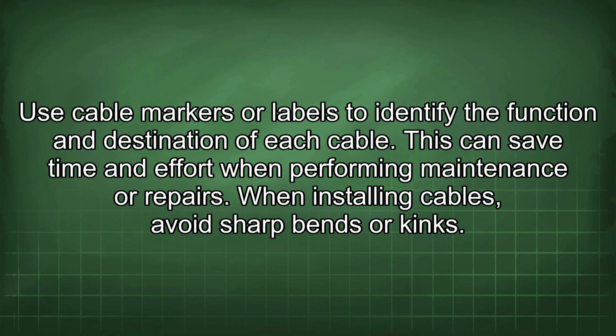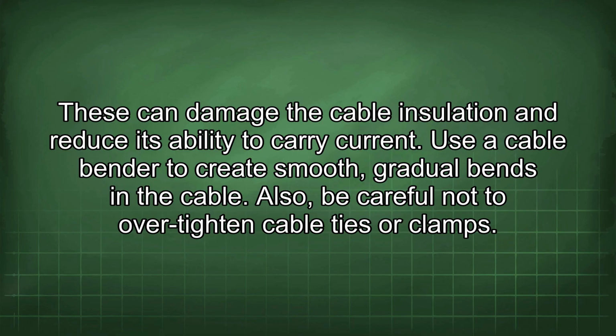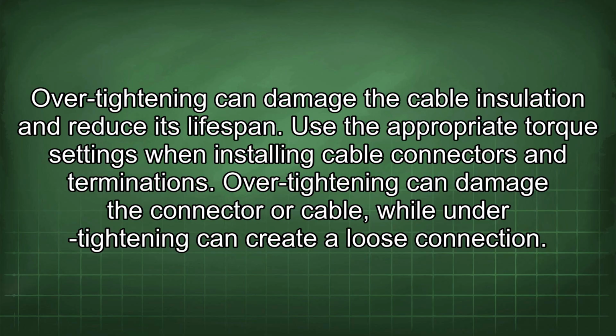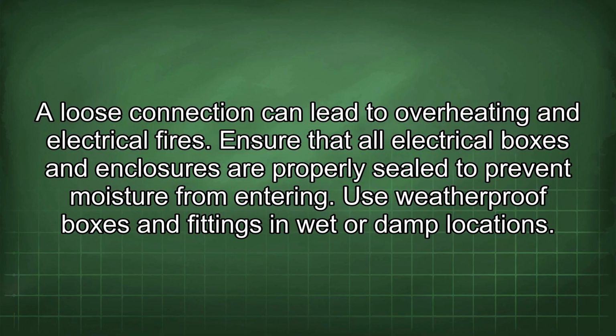When installing cables, avoid sharp bends or kinks. These can damage the cable insulation and reduce its ability to carry current. Use a cable bender to create smooth, gradual bends in the cable. Also, be careful not to over-tighten cable ties or clamps. Over-tightening can damage the cable insulation and reduce its lifespan. Use the appropriate torque settings when installing cable connectors and terminations. Over-tightening can damage the connector or cable, while under-tightening can create a loose connection. A loose connection can lead to overheating and electrical fires.